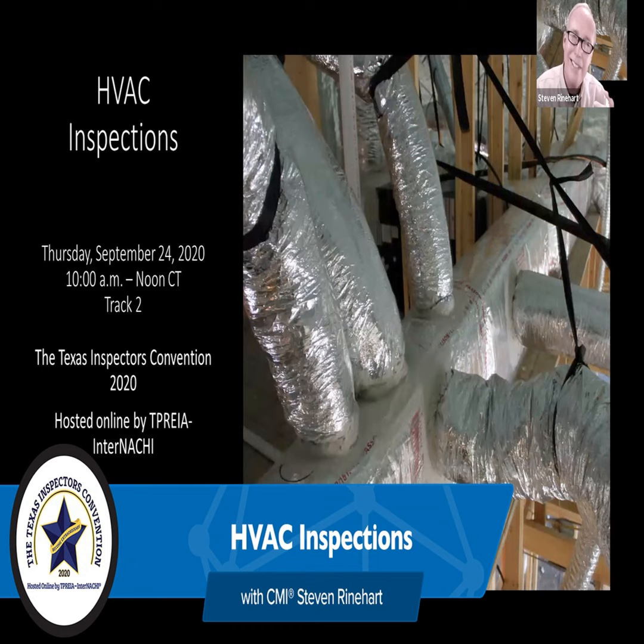Flex duct came on board early 80s in our area. So we went from rigid duct to the first gray flex duct, which was not compatible with UV light. From about 82 to 85, it was used in a lot of houses around my area. If those are still there, they peeled like a snakeskin, and it's left the insulation and maybe the duct exposed. Very common, mid 80s house. We see it all the time.